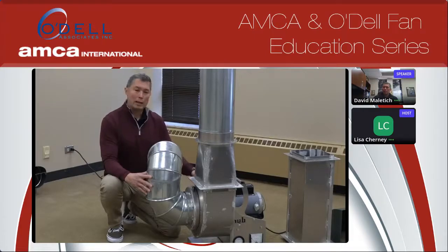So if we were actually able to take an amp reading and do an efficiency calc, even though this fan's producing more pressure, it's doing it much less efficiently. Horsepower has actually gone up, and that's kind of evident in the amount of noise that the fan's producing.